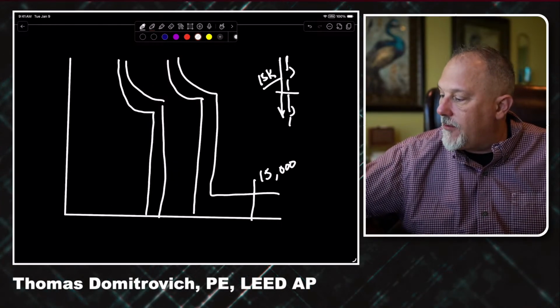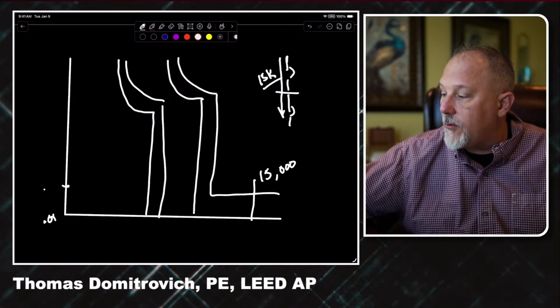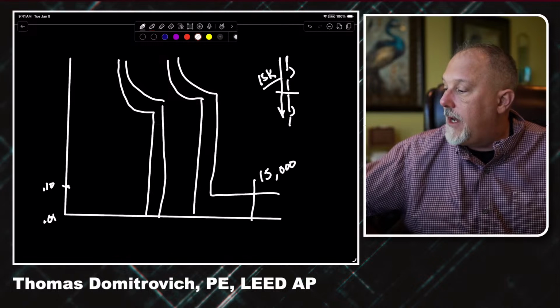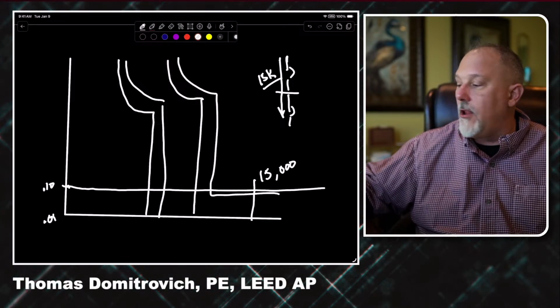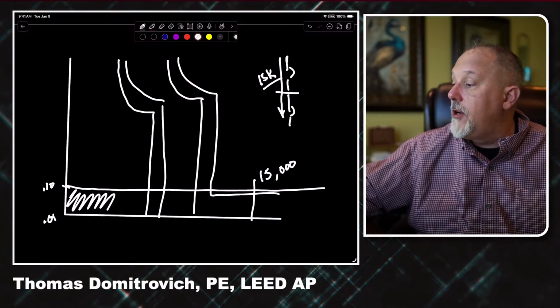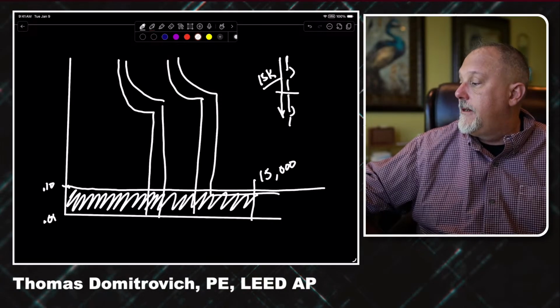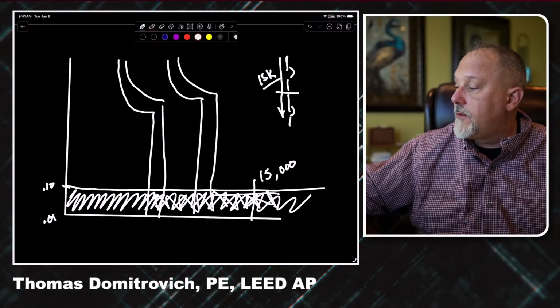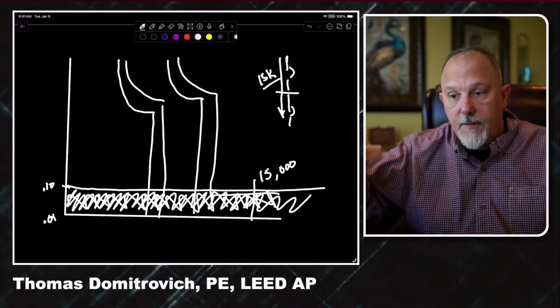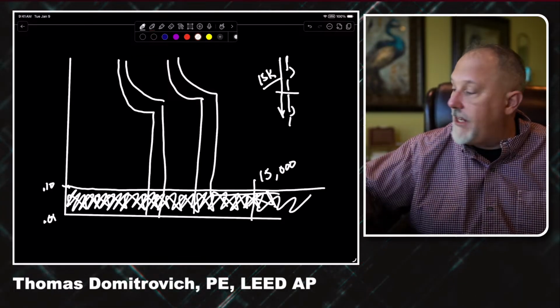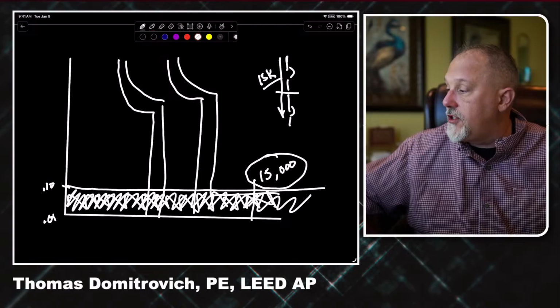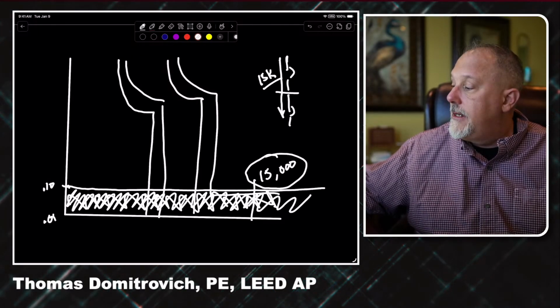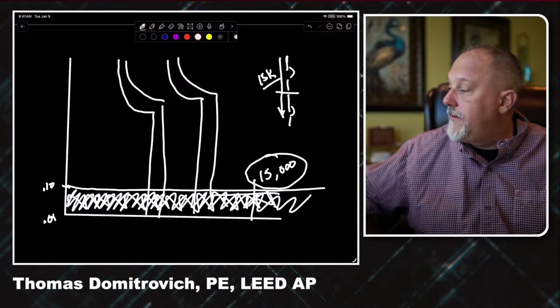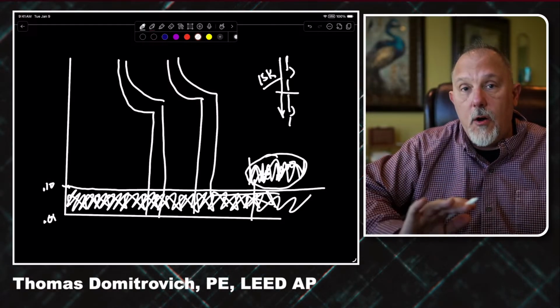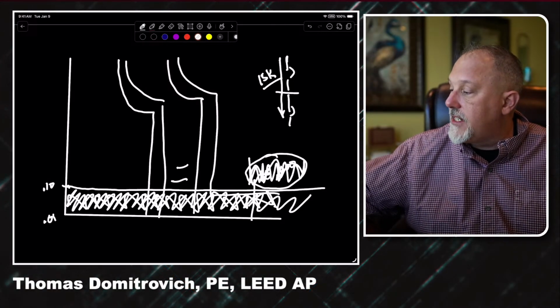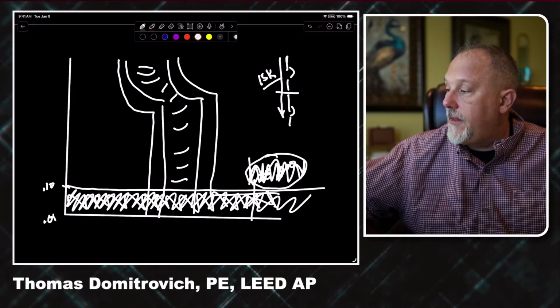When I do a 0.1 second, remember this is 0.01. If I'm doing a 0.1 second review, this is what I do. I take my 0.1 seconds, draw it all the way around over, and I ignore everything below that 0.1 seconds. I do this. I completely forget about the portion of the curve. Now, it could be that I have a foot coming over or whatnot. And then what I do, because this is a problem, because I know those two breakers with 15,000 amps going through both of them, I have to do something with the 15,000 amps. We ignore that. And all 0.1 seconds is doing is looking for separation of these curves in the overload region.